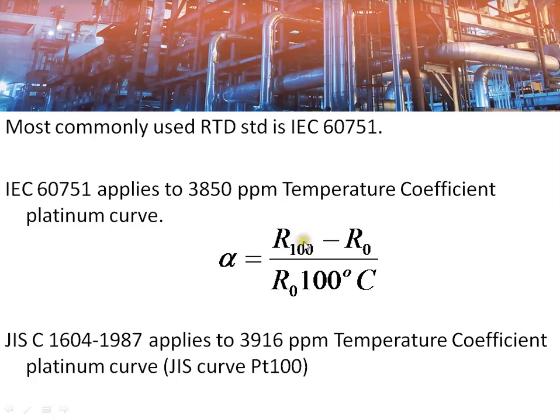The equation is: R100 minus R0, divided by R0, multiplied by 100 degrees centigrade, where R100 is the resistance at 100°C and R0 is the resistance at 0°C. Other standards are available for RTDs, like JIS C 1604-1987, which applies to platinum RTDs with a 3916 ppm temperature coefficient of resistance. Later versions of that standard also conform to IEC 751. Other temperature coefficients of resistance used for platinum RTDs are 3750 ppm and 3770 ppm.